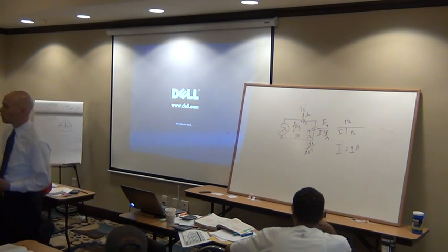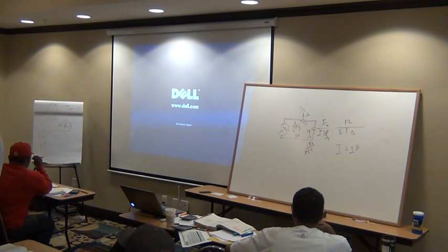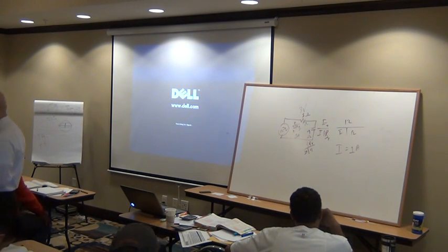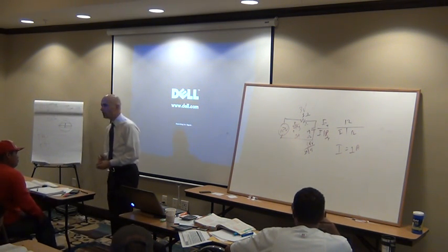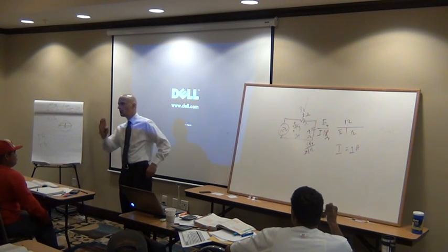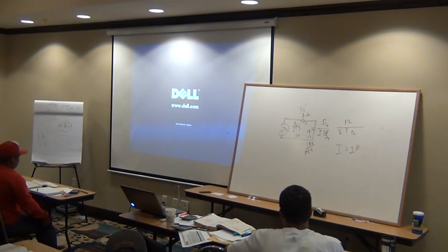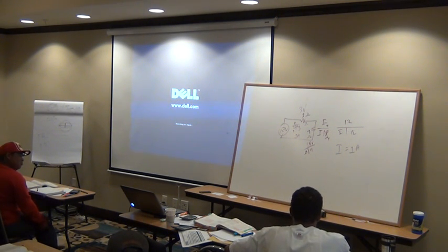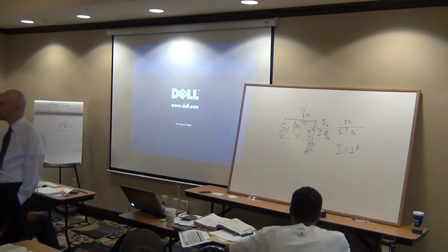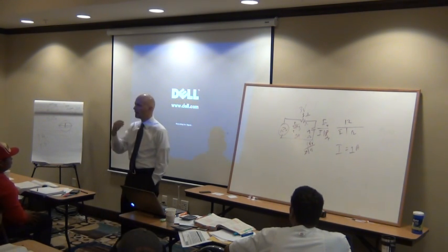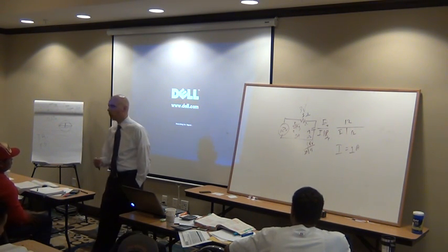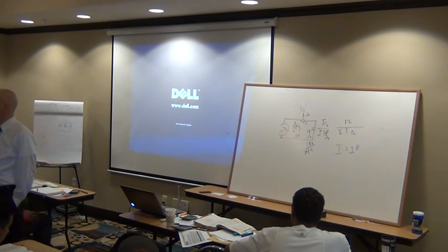So you can really look at a conduit question. In general, you will have conduit fill, flat out. Not many, but there's 1 or 2 off the top of my head that have been recent questions that have to do with some number 8s run into schedule 40 PVC, and it comes up into the distribution panel as schedule 80. I think they tell you it's a number 8 wire fed into a residential application. They don't tell you the ampacity, or they tell you the amperage, and you have to go to the table and find out what size wire you would put in it, and then multiply that times however many wires you normally have in a residential feed. And then size the conduit.